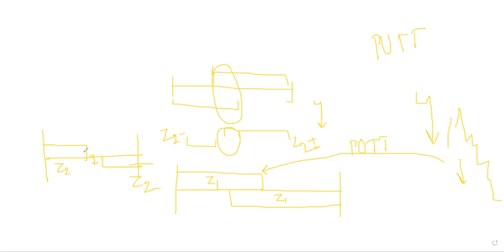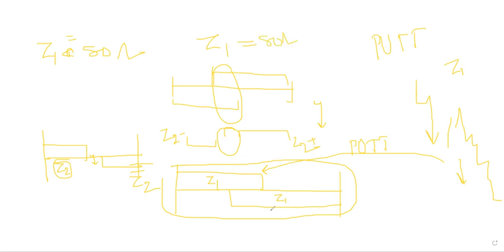I am just making this imaginary. No, one minute. Suppose you are saying that if the fault is below 80%, it is a zone 1 fault, correct? Now you are putting for breaker A some portion, maybe 50 to 60%. You are considering this as a fixed one. But now I am calculating the impedance. Suppose the impedance of this line is 80 ohms, then it is zone 1. And for this zone 1 also, suppose 80 ohms. Let's assume below 10 to 15 ohms only of the total line length.